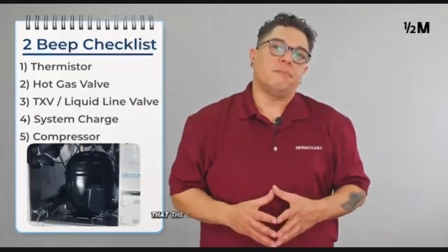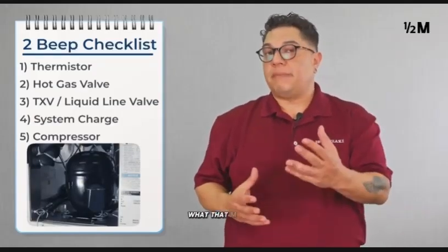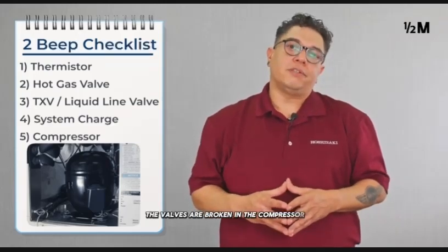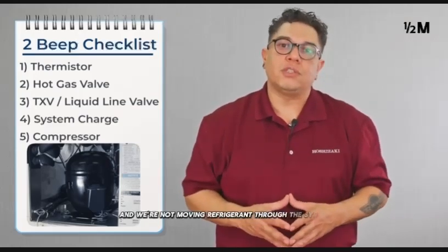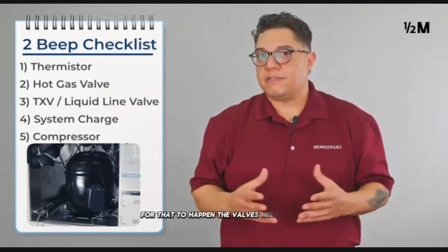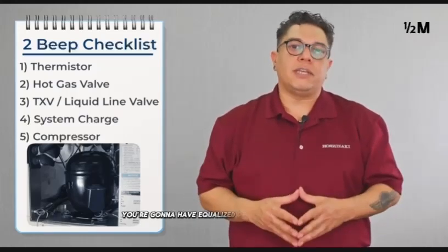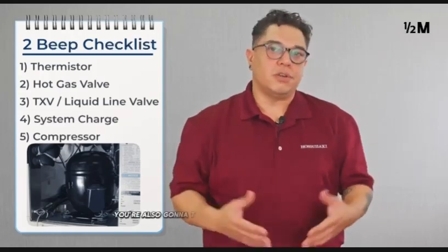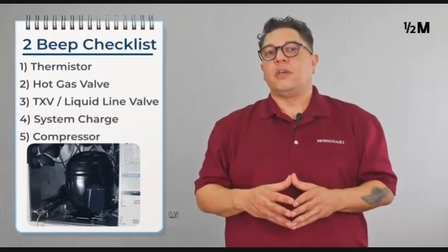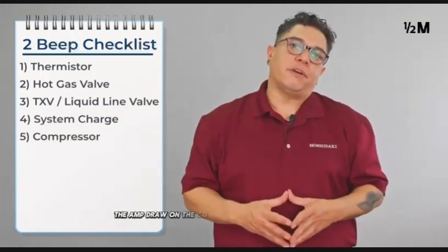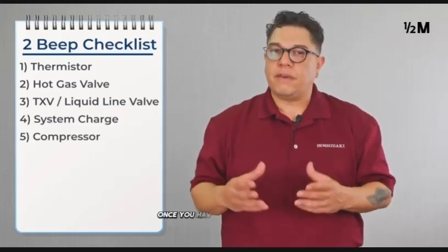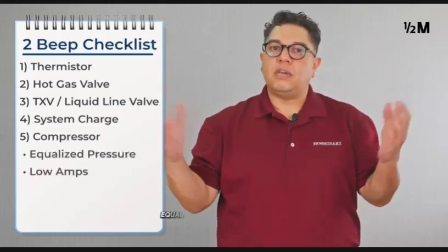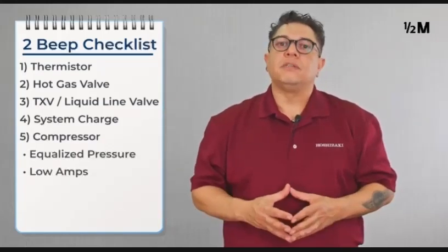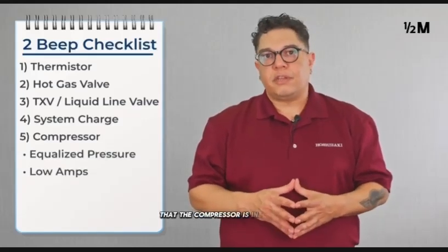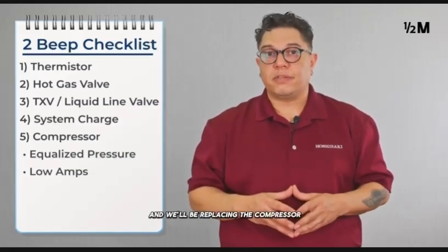Once we confirm that the charge is accurate on the machine, then we can move over to the compressor. We're going to confirm that the compressor is inefficient. What that means is the valves are broken in the compressor and we're not moving refrigerant through the system. For that to happen, the valves need to be broken. You're going to have equalized pressures on both sides. And to confirm that the valves are broken, you're also going to take an amp draw on the compressor. With the valves being broken, the amp draw on the compressor is going to be very low. Once you have two of those items, equalized pressures and low amps, we'll be able to confirm that the compressor is inefficient, and we'll be replacing the compressor at that point.